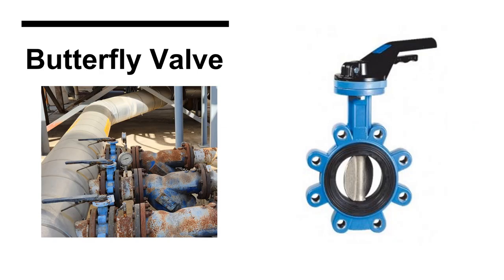Butterfly valves are not typically used in refrigeration systems; however, they are frequently used to control the flow of secondary coolants such as glycol solutions. Butterfly valves are generally designed for bi-directional fluid flow. Typically, they are installed so that the handle is parallel to the disc, with the handle pointing along the line of fluid flow. Like ball valves, they are either fully open or fully closed and require a quarter turn to operate.